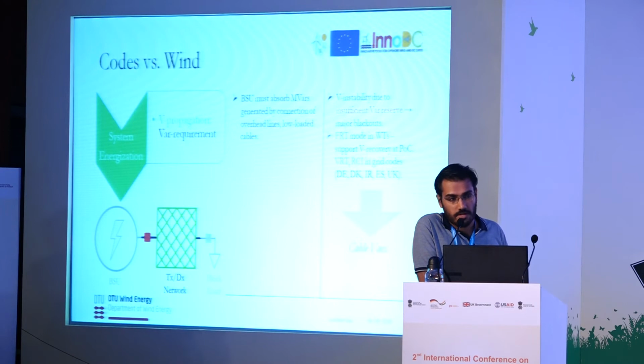As far as system energization is concerned, a Blackstart unit is required to absorb the megavars, the capacitive reactive power that is generated by the connection of low-loaded lines and cables. Wind turbines, due to their state-of-the-art power electronics interface, can provide quite fast voltage control, and also very new grid codes are showing voltage ride-through and reactive current injection requirements. So there is very good capability matching here.